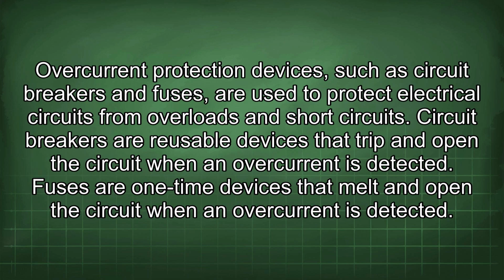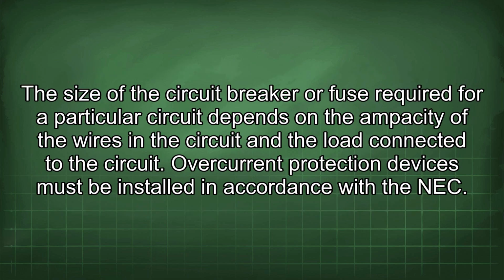Overcurrent protection devices, such as circuit breakers and fuses, are used to protect electrical circuits from overloads and short circuits. Circuit breakers are reusable devices that trip and open the circuit when an overcurrent is detected. Fuses are one-time devices that melt and open the circuit when an overcurrent is detected. The size of the circuit breaker or fuse required for a particular circuit depends on the ampacity of the wires in the circuit and the load connected to the circuit. Overcurrent protection devices must be installed in accordance with the NEC.